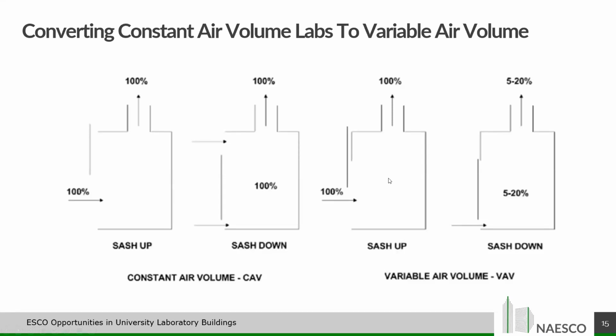When you go to variable air volume, when the sash is up, you've got the same scenario as the constant air volume hood, that you've got 100% of the air coming through the sash opening, maintaining your face velocity and going up through the duct and out of the building. But when you close your sash, you're able to greatly reduce the amount of air being exhausted through that fume hood. It needs to be at a minimum 150 air changes per hour of the volume inside the fume hood. That's about an 85% reduction of exhaust air from when that sash is up, or from when the fume hood is, if it was constant air volume. Now, this is one fume hood. You can imagine a lab that's got a dozen fume hoods in it, and general exhaust and all of that. And if it's all variable air volume, you have a tremendous reduction in the amount of exhaust air coming from that lab. And more importantly, the amount of outdoor air that needs to be heated, cooled, and dehumidified to make up for all that exhaust.